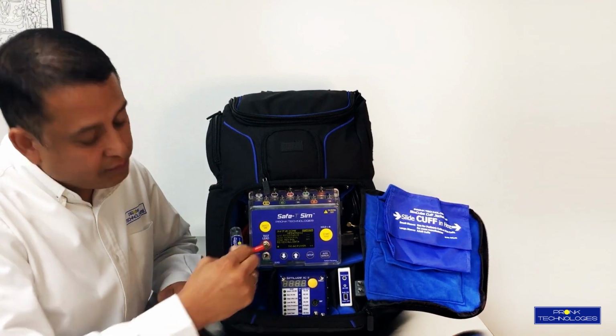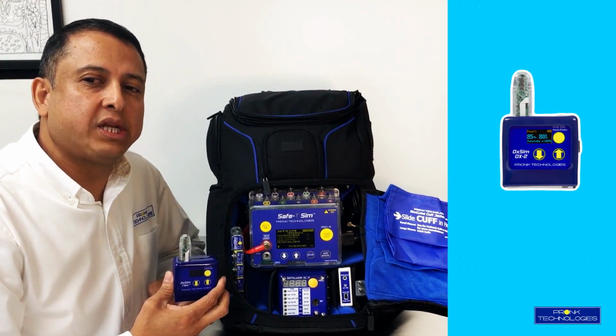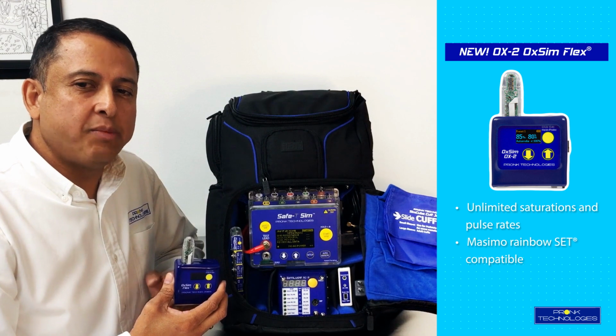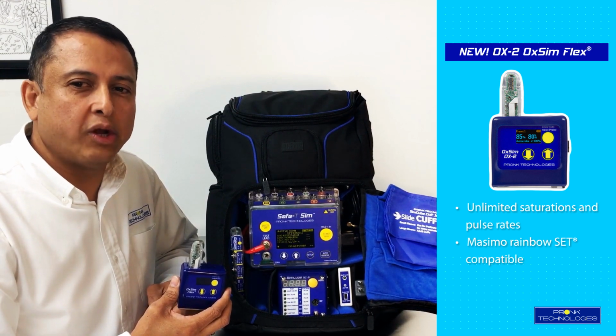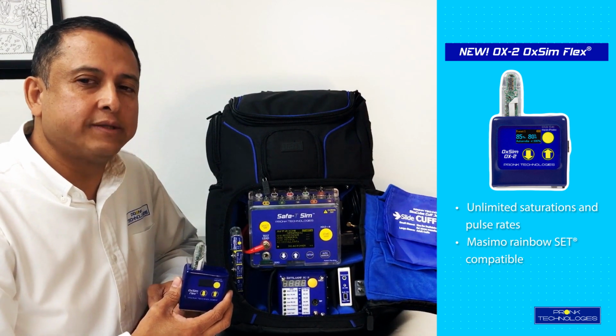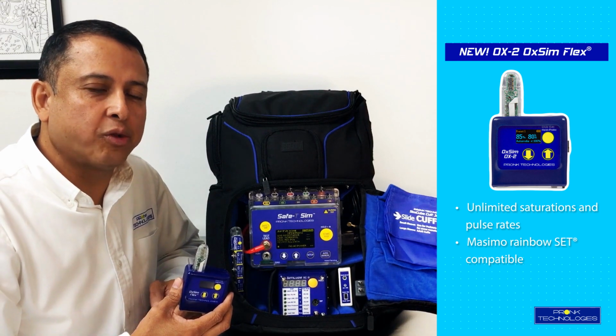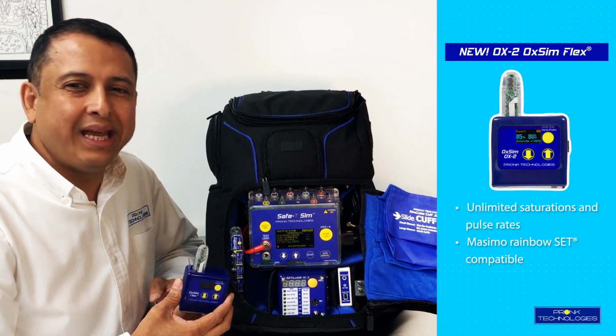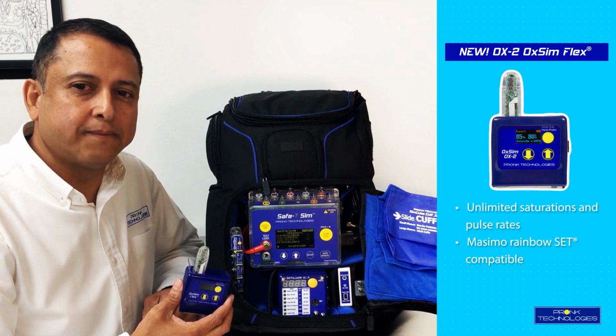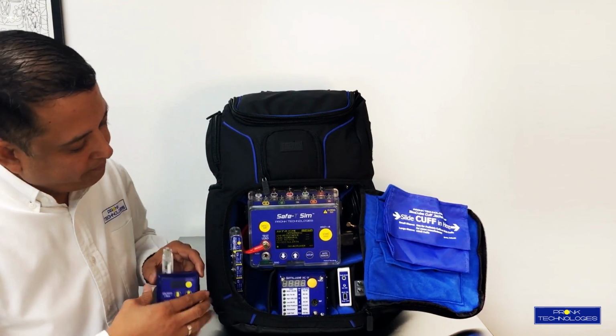The OxSim Flex SpO2 simulator provides the ability to test the SpO2 parameter, to simulate any saturation, pulse rate, and perfusion level in 1-digit increments. It automatically detects the manufacturer of the pulse ox technology, eliminating the need to manually select the manufacturer under test. It also runs on a single AA battery.